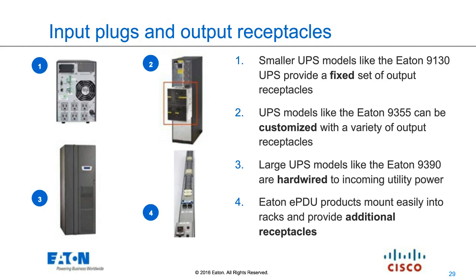Regardless of which UPS you pick within that range, and the Eaton Care team can help you make the right decision there, as long as there's a network card installed, Intelligent Power Manager will allow you to map through the GUI. You create a linkage between the UPS that's powering the server, and then, again through the GUI, a script that dictates what that server should do after a certain amount of time on battery—be it shutdown, live migration, or maybe using Site Recovery Manager, which is another thing we can do as part of disaster avoidance. IPM is then responsible for sending that shutdown command to the server in response to the UPS, all configured as a policy definition combined with an action definition within our platform.